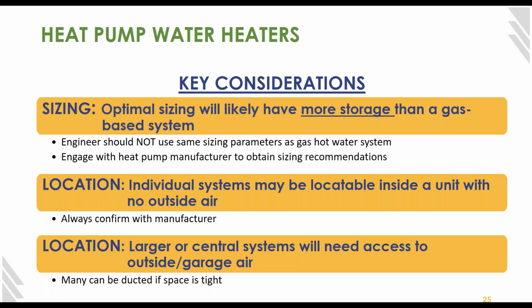First is sizing. It's really important to understand that the optimal sizing for a heat pump water heating system is likely to require more storage than a gas-based system. So it's critical that a design engineer not use the same sizing parameters they would use for a gas hot water system. A good way to avoid sizing issues is to engage with the heat pump manufacturer to obtain their sizing recommendations.